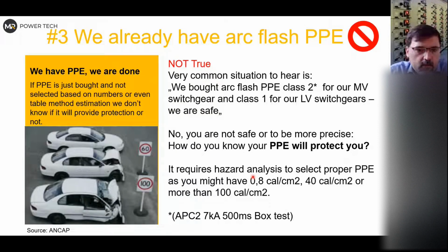And I hear it very often in Europe, for example, where we use PPE class 1, class 2, which is box method testing. Not popular in the US, it's popular in Europe. And you very often hear people tell you we have PPE class 2 for medium voltage switchgears and PPE class 1 for low voltage switchgears, and we are safe. In fact, it's completely the opposite, because you very often expect much higher energy on low voltage switchgear or installation than on medium voltage. So the selection is not correct, but despite that, you don't know your numbers, you don't know the incident energy, whether it is 0.8, 40 calories, or maybe 100 calories. And in the US, you can see something like PPE category 2, up to 8 calories, when people say, oh, we bought some basic PPE and we are done.